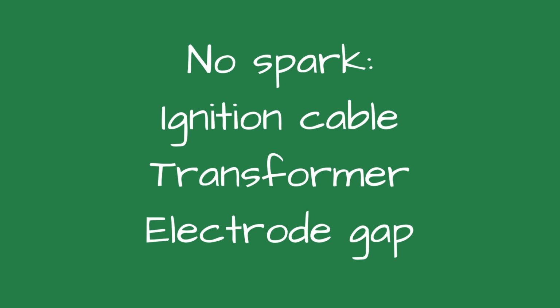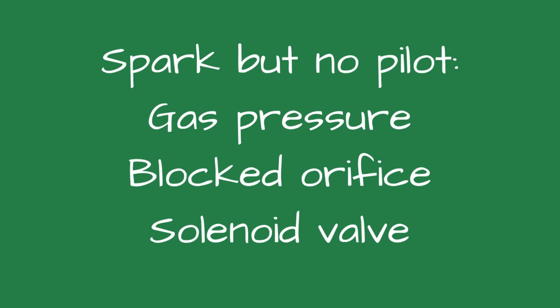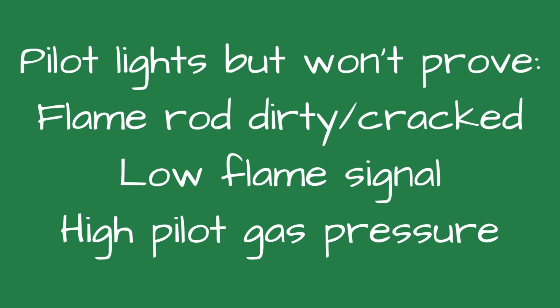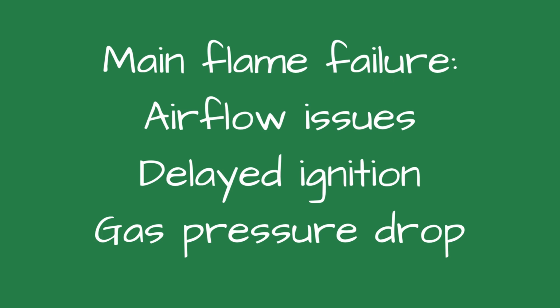Here's a quick reference troubleshooting flow chart. If you have no spark, look at the ignition cable, transformer, or electrode gap. If you have a spark but no pilot, check your gas pressure, blocked orifice, or solenoid valve. If the pilot lights but won't prove, look at the flame rod for being dirty or cracked, low signal, or high pilot pressure. If the main flame fails after startup, look for airflow issues, delayed ignition, or gas pressure drop.